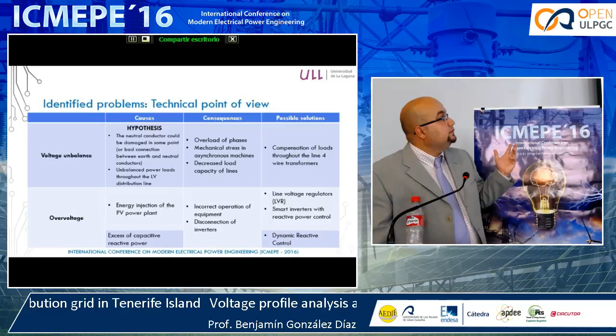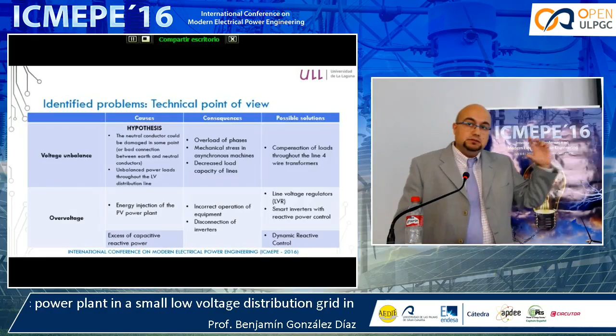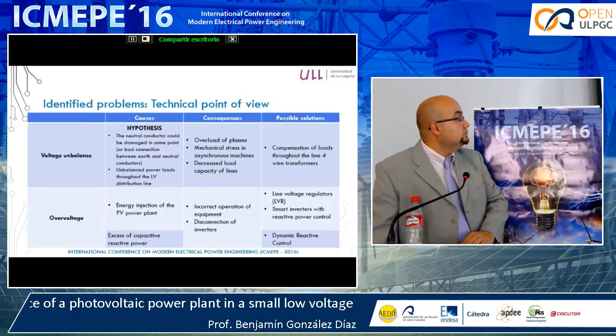In the case of the overvoltage, we think that the culprit is the energy injection of the PV power plant. But we also have an excess of capacitive reactive power. This translates into incorrect operation of the equipment and the disconnection of the inverters. We had a look at the data registration of the inverters, and every 4 seconds the inverters were stopped because they were detecting an overload and undervoltage all the time. So a possible solution is to use a line voltage regulator, also smart inverters, or also a dynamic reactive control in order to decrease the capacitive reactive power of the line.